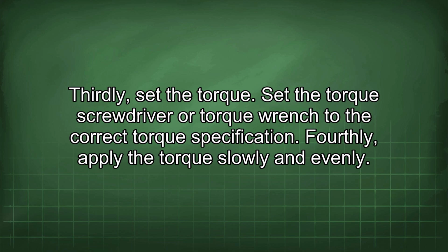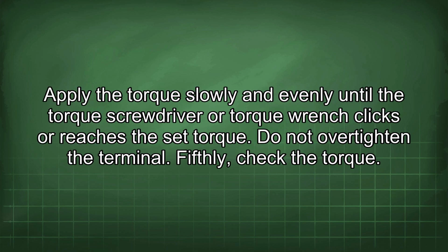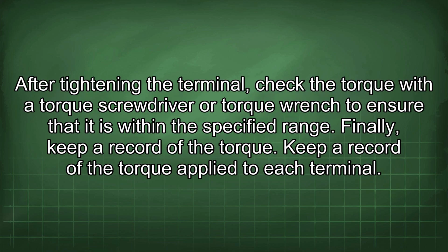Fourthly, apply the torque slowly and evenly. Apply the torque slowly and evenly until the torque screwdriver or torque wrench clicks or reaches the set torque. Do not over-tighten the terminal. Fifthly, check the torque. After tightening the terminal, check the torque with a torque screwdriver or torque wrench to ensure that it is within the specified range.